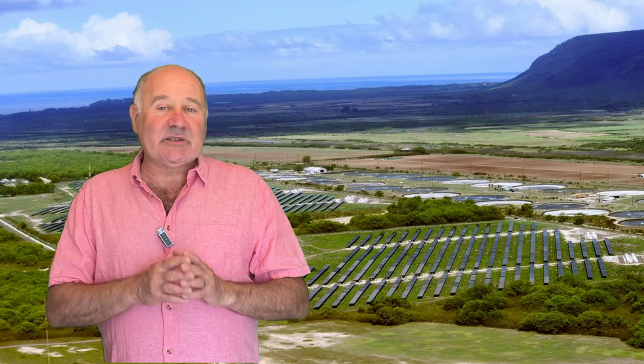There's a need for studies and computer simulations to optimize the design and use of grid-forming inverters. For instance, how can we change the design of grid-following inverters such that they increase reliability? Maybe if the frequency is going up, we use a random number generator so that only some of the inverters go offline rather than all of them. How many grid-forming inverters do we need to keep the grid stable? How do multiple grid-forming inverters work together rather than fight over the proper phase?